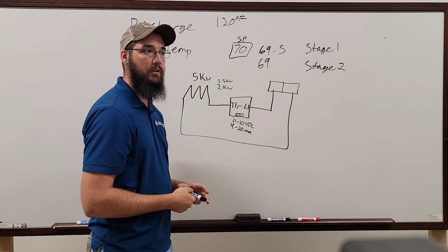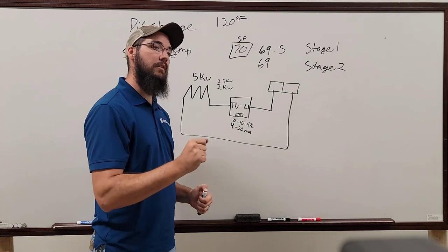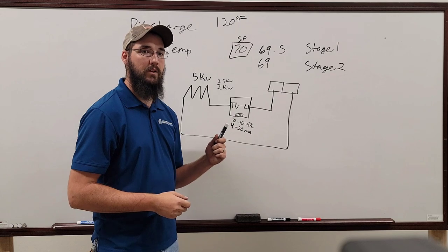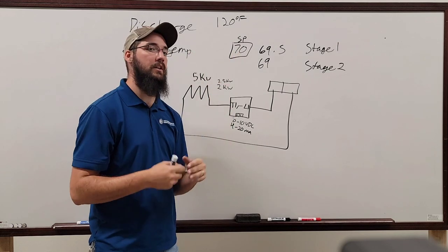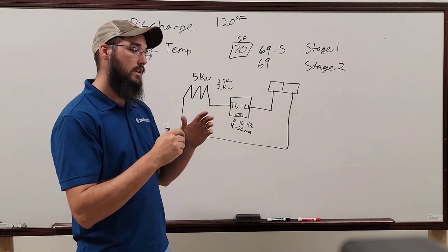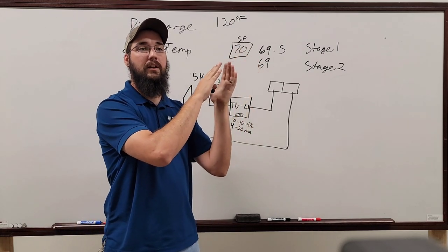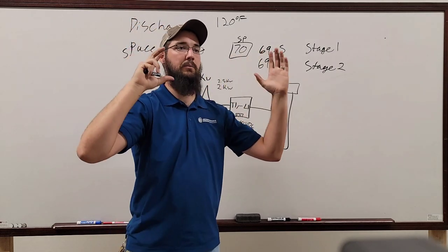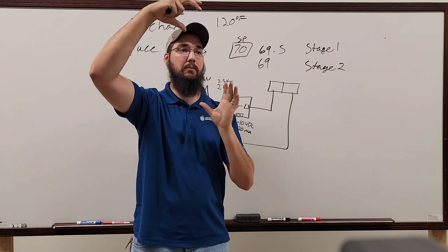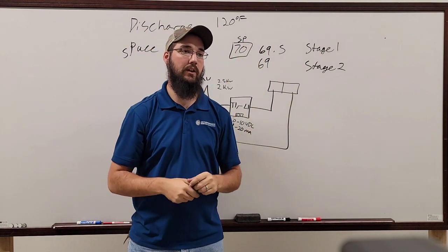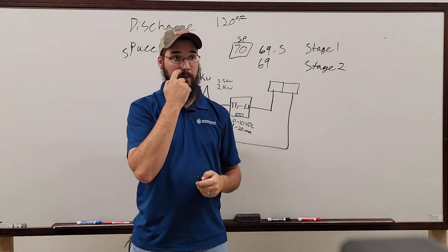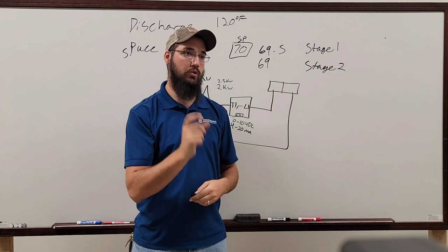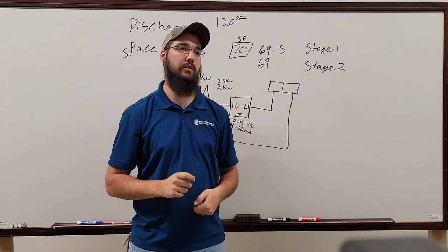That makes sense. Now, an immediate indicator without ever opening a control panel that you have an SCR is you'll have a heat sink. Whenever you are walking around or you pop a ceiling tile, whatever it is, if you look on the outside of the control cabinet, you'll see this big, usually aluminum, block of metal with a bunch of fins sticking out of the side of the control panel. A lot of times they end up getting painted over. That is the heat sink that helps protect that SCR from overheating. So as soon as you see that, you should automatically know what you're dealing with.